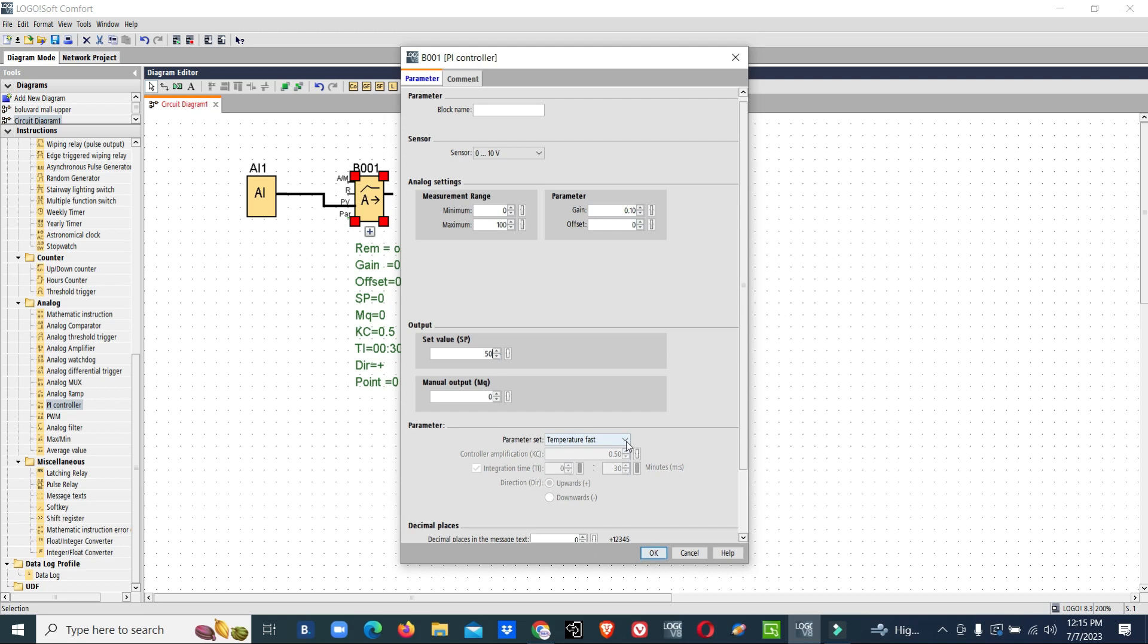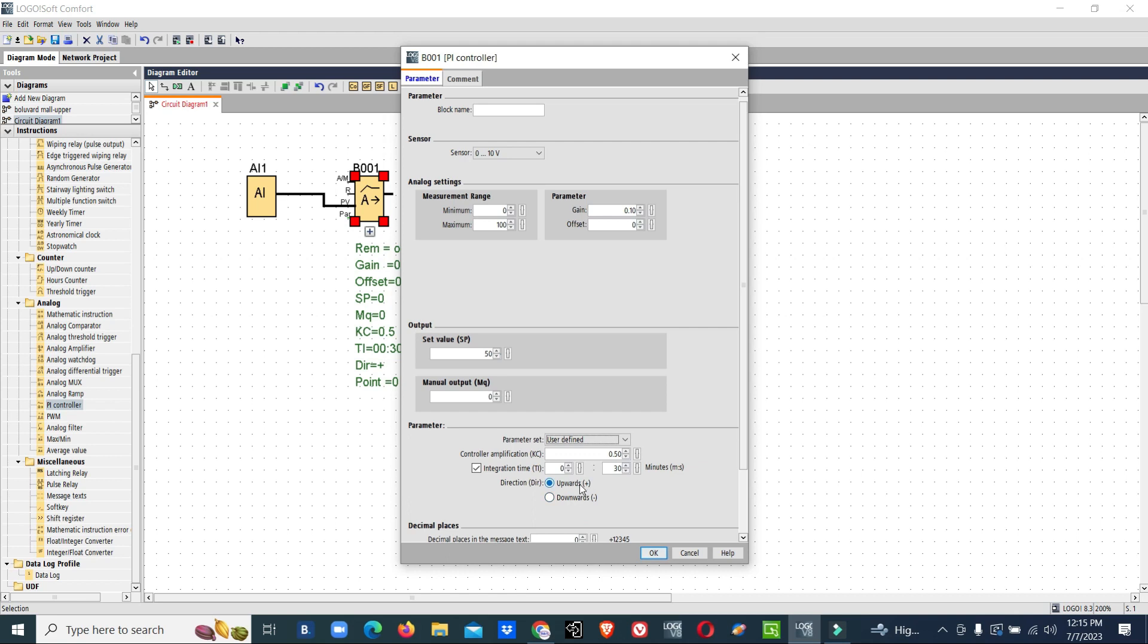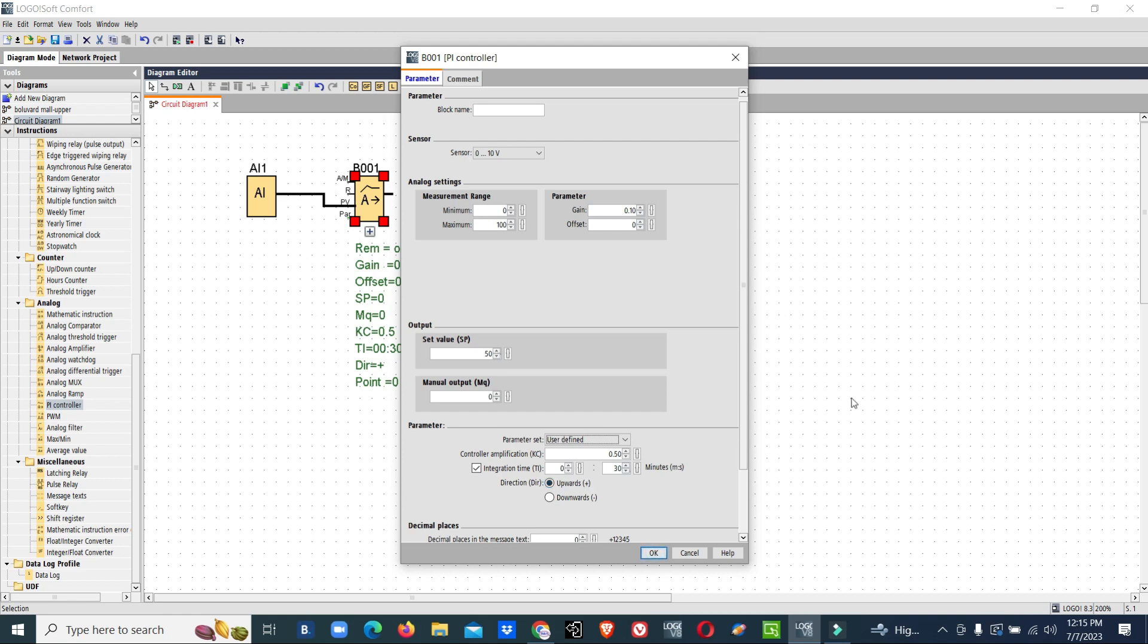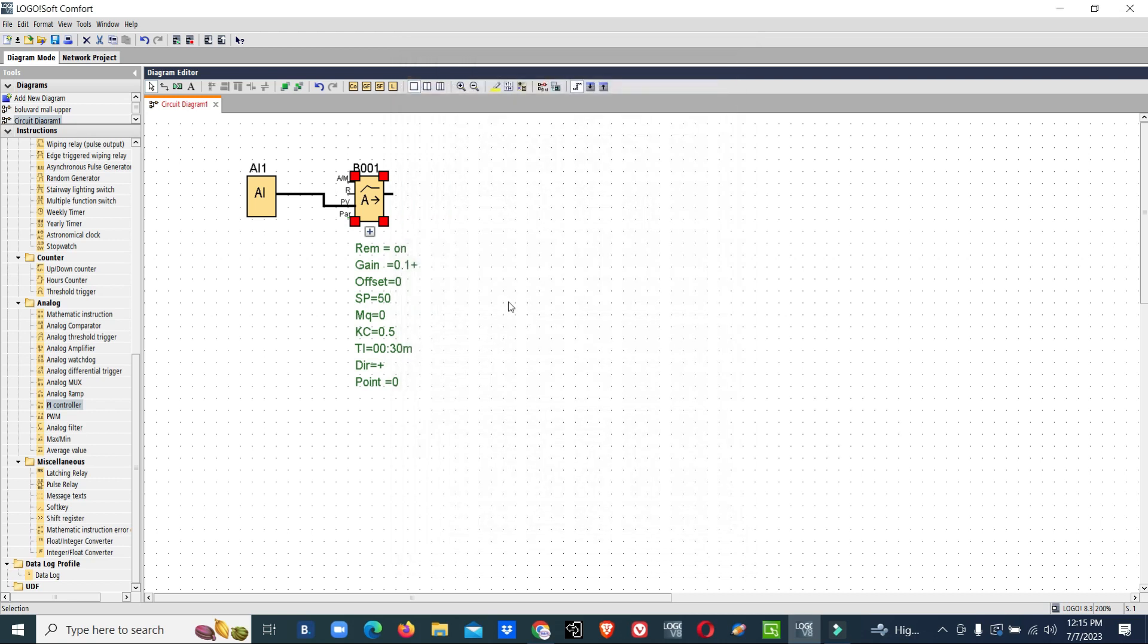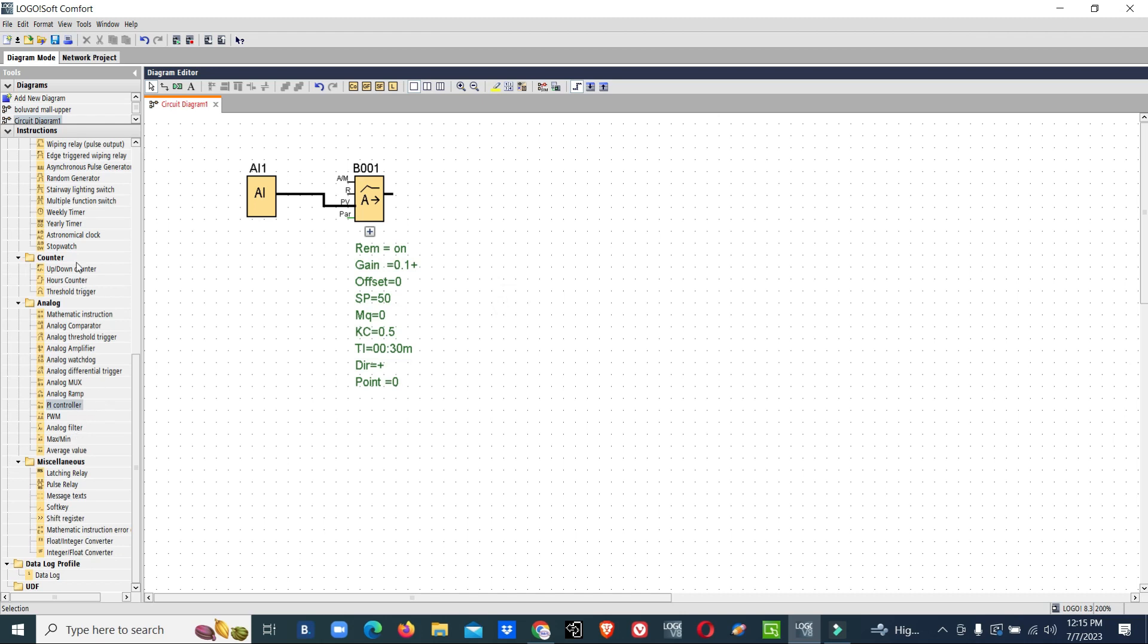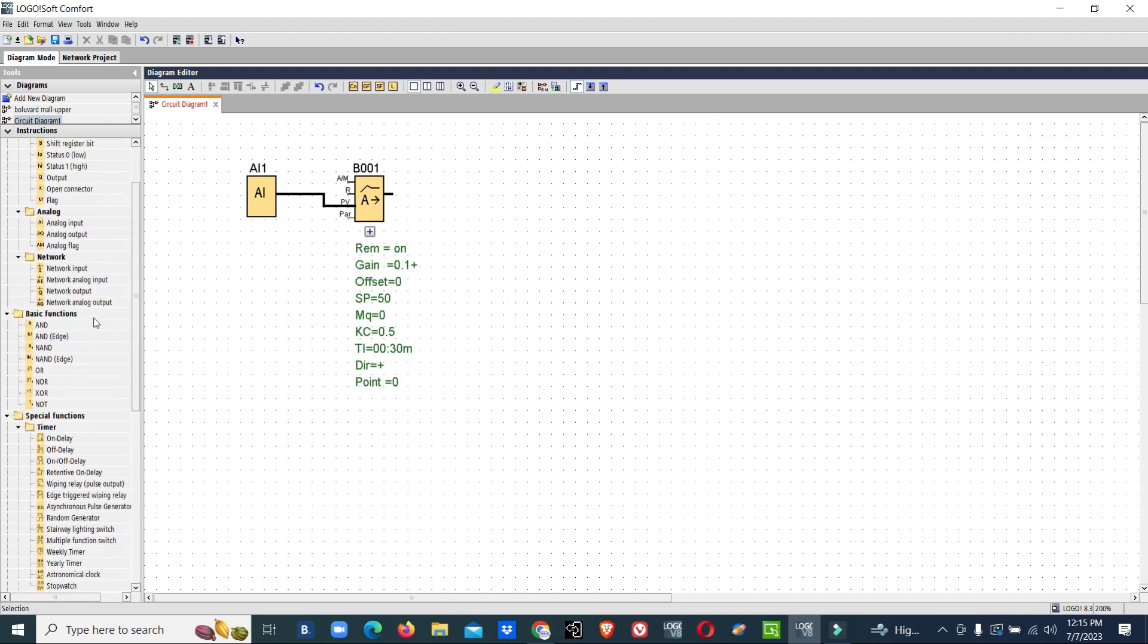Go with user defined. Here we can select our type of PID control, upwards or downwards. We want to maintain pressure. When the pressure goes below the setpoint, it should match, so the PID should be in upwards. Now we will connect analog output.